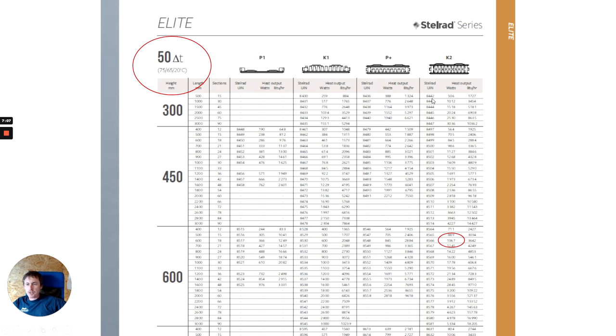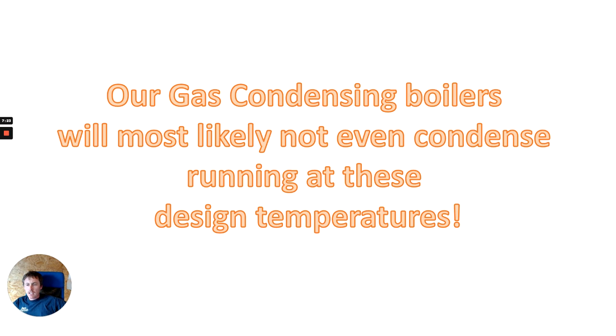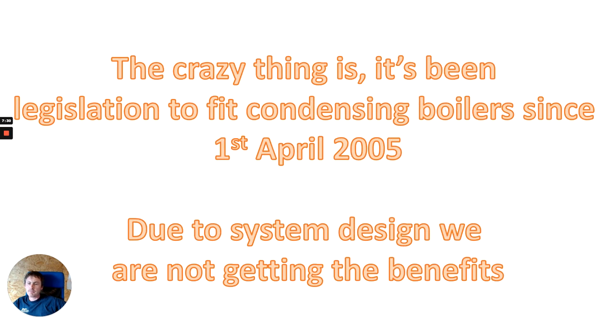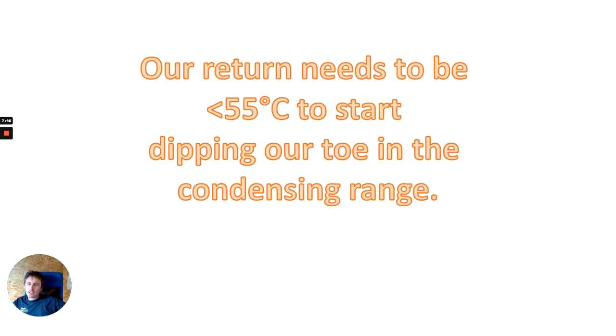Looking at Screwfix, we've noted the watt output for a 600×600 K2 double convector panel radiator: 1,056 watts — and if you note in the specification, it's listed at delta T 50. On the Stelrad website, also at DT50, you can see they've stated the flow, return, and room temperature — a 10-degree difference and 20°C room temperature — with about a 10-watt difference between the two catalogues for a like-for-like K2. Our gas condensing boilers will most likely not even condense running at these design temperatures at minus 3 outside. The crazy thing is it's been legislation to fit condensing boilers since 1st April 2005, yet due to system design we're not getting the benefits. Our return needs to be less than 55°C to start dipping into the condensing range.